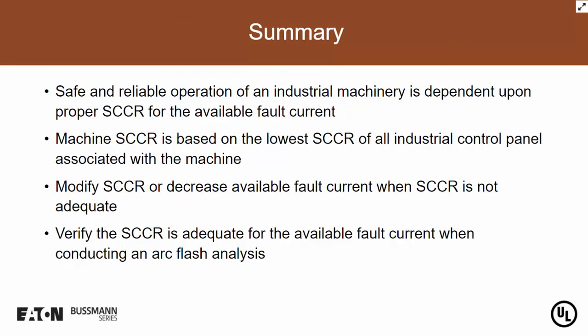All right, so in summary, let's group all this together again. What did we learn today? Safe and reliable operation of industrial machinery depends upon the proper SCCR for the available fault current. We're talking about electrical hazards and electrical safety. We want to make sure that the SCCR is adequate for the available fault current, for operators as well as electricians, the qualified person going into the panel to troubleshoot. We want to make sure he's properly protected, and that the operator doesn't have to worry if a fault does come down the line and something happens to that panel.